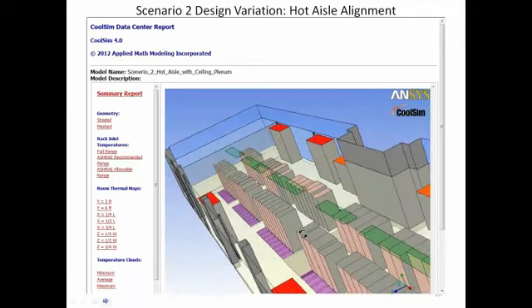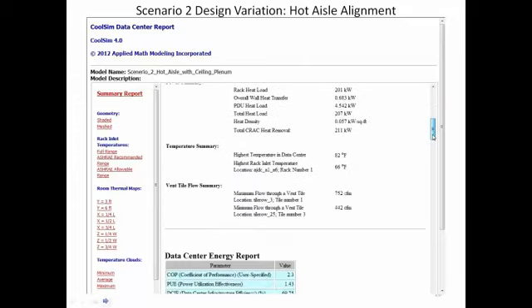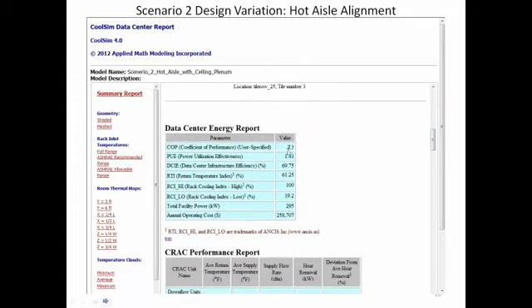If we take a look at the summary report, again, everything remains pretty much the same until we get down here. We're still assuming 2.3 for coefficient of performance. The PUE remains the same. But your RTI here, 61, is pretty close to where we were before, again because we haven't changed the airflow. But the RCI is now 100%, which means you've got no racks in trouble. And the RCI low, still 19, still too cold, but things are improving. It looks to me like the hot aisle configuration is behaving better by a little.